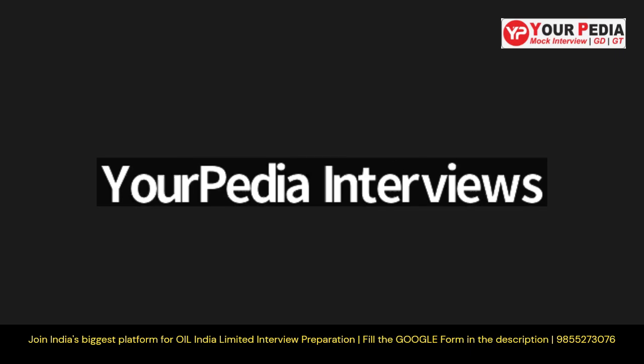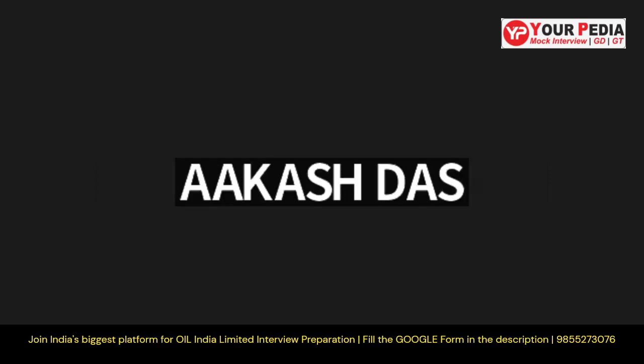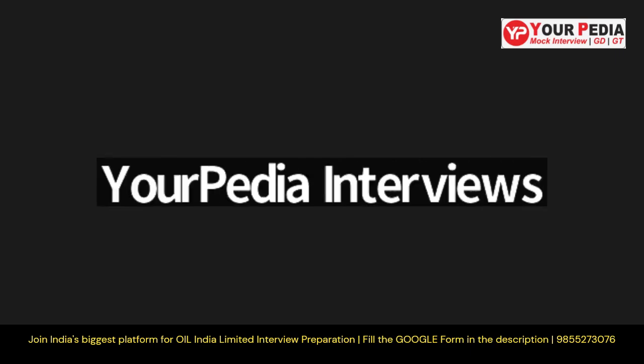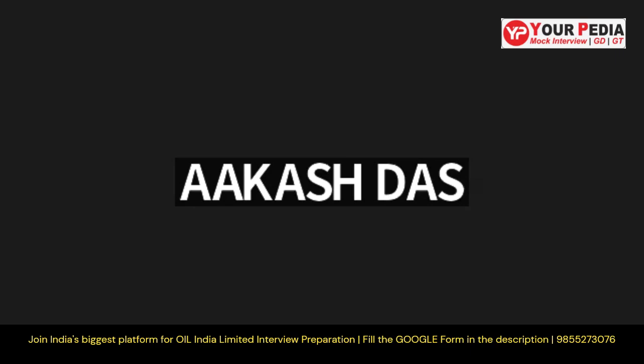What is the mathematical notation of steady state stability? Sir, the mathematical notation is P equals E V by X sine delta, where E is the EMF, V is the voltage, X is the reactance and delta is the load angle. The maximum steady state stability occurs at delta 90°, where P equals E V by X.